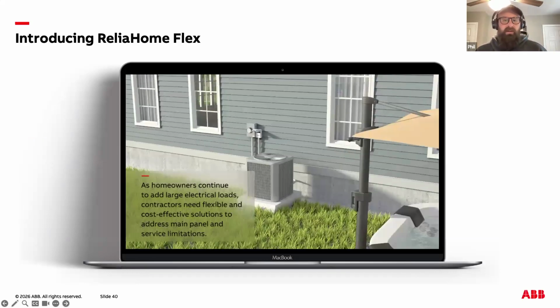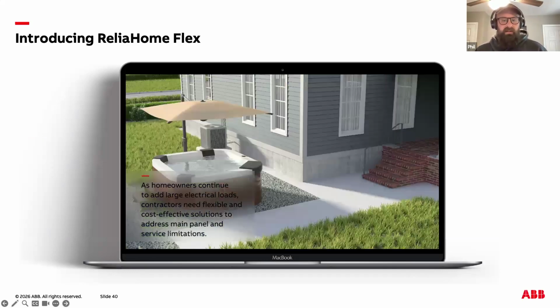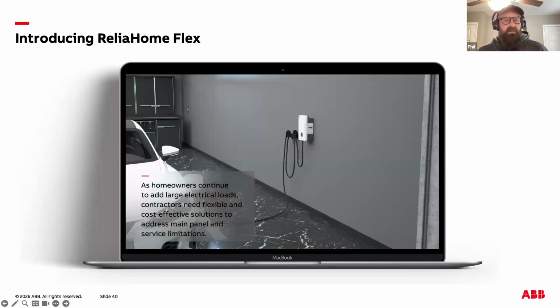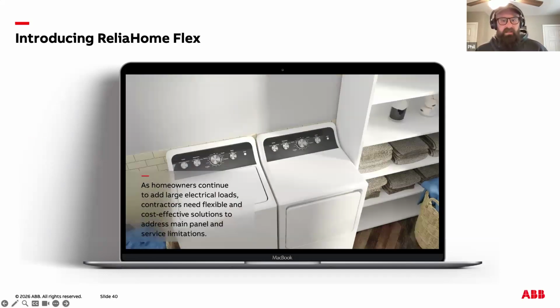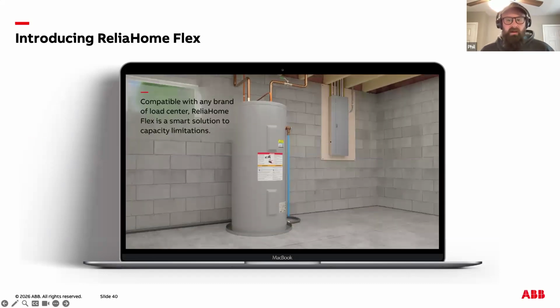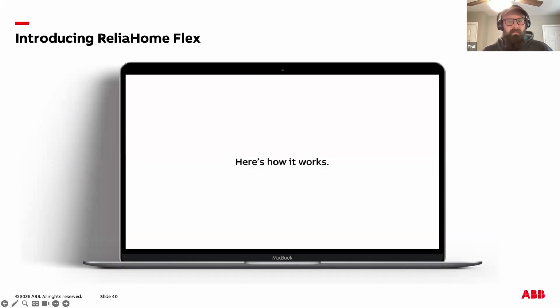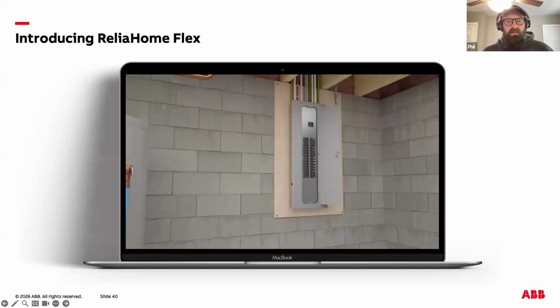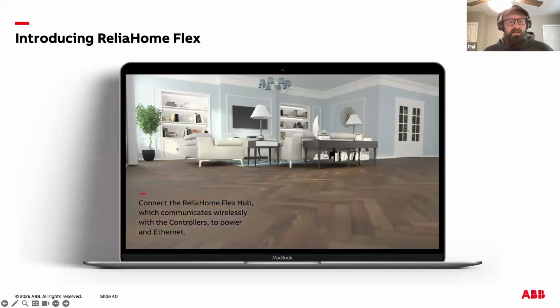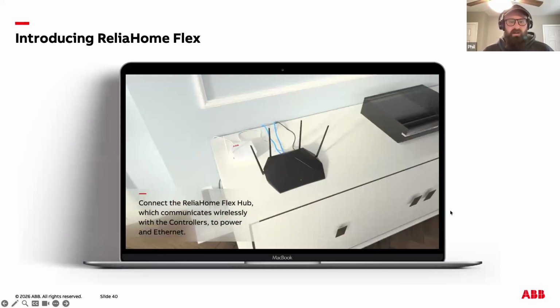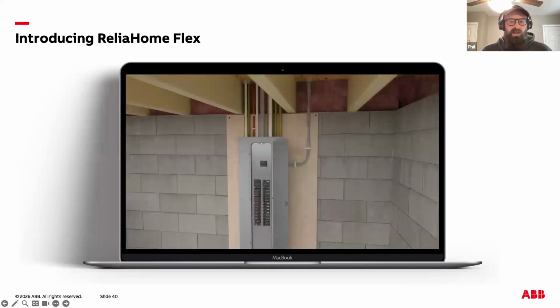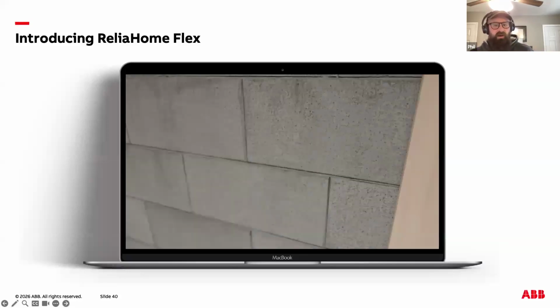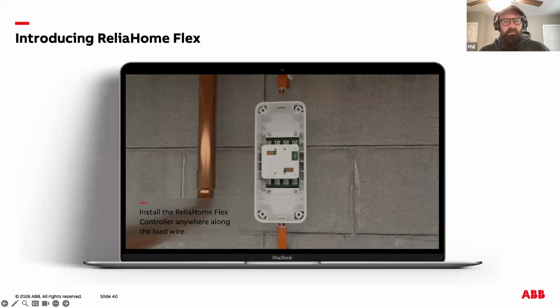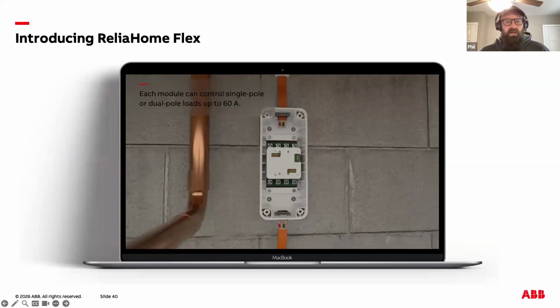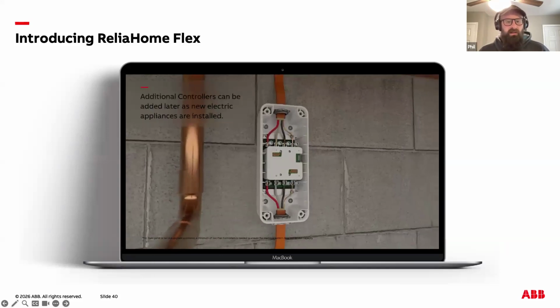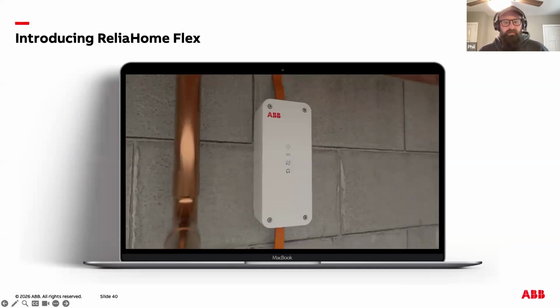As homeowners continue to electrify, the need for flexible and cost-effective solutions arises to address main panel and service limitations. The Flex system is compatible with any brand of load center or breaker manufacturer and consists of the hub and controllers. The hub connects to the home's Wi-Fi router and communicates wirelessly with the controllers. It is as simple as just plugging it in. Controllers are installed anywhere along the load wire, providing power for the load you want to control. Each controller can support 120 or 240 volt loads up to 60 amps. Additional controllers can be added later as new electric appliances are installed.